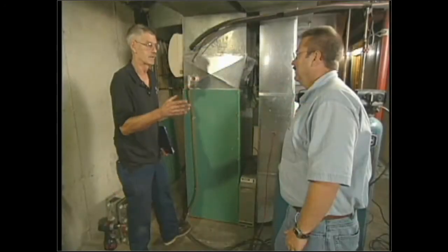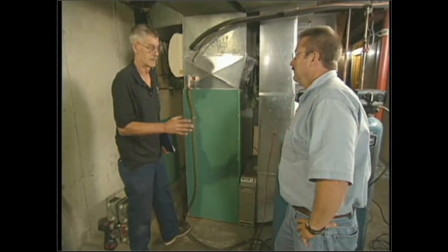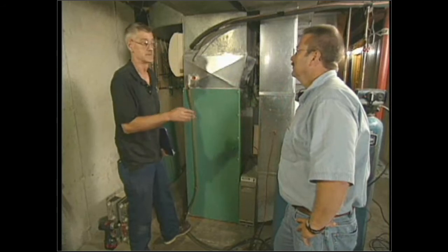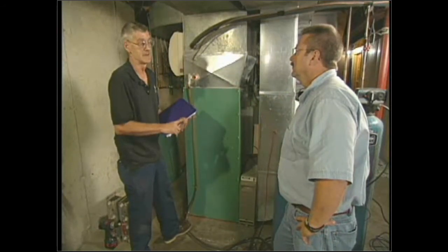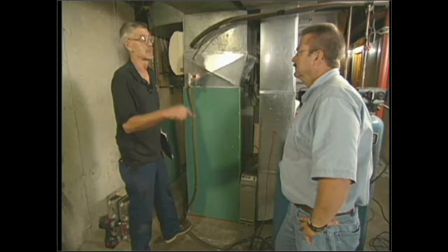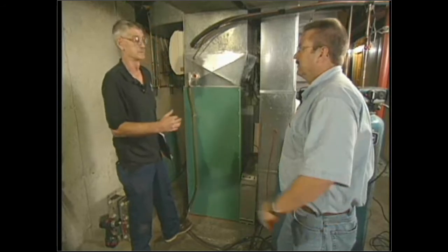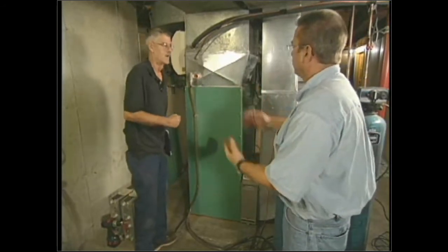As with all furnaces, we have to test airflow. The two tests that we use to do that are exactly the same tests we do on a 70, 80, and a 90. We do a static pressure test, and we do a flow meter test. Okay, let's start with the static pressure test. What's involved with that?